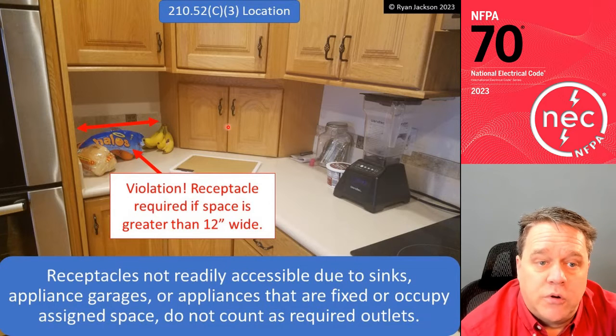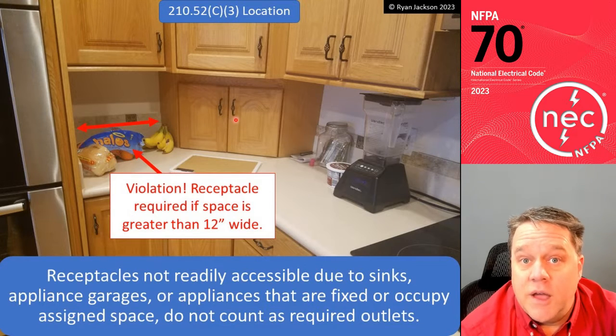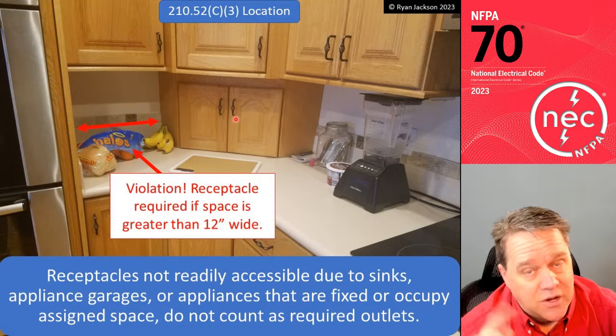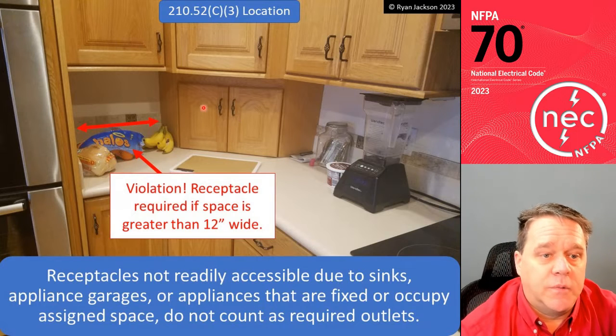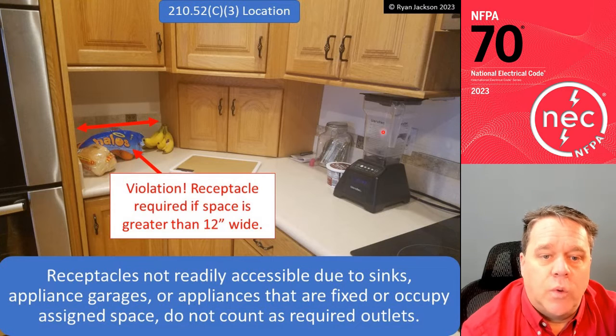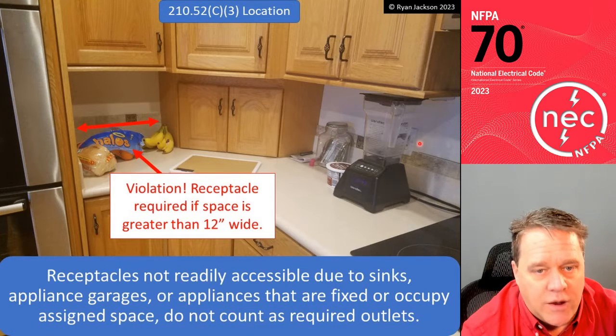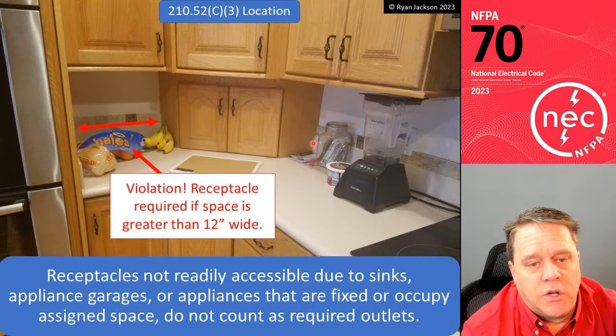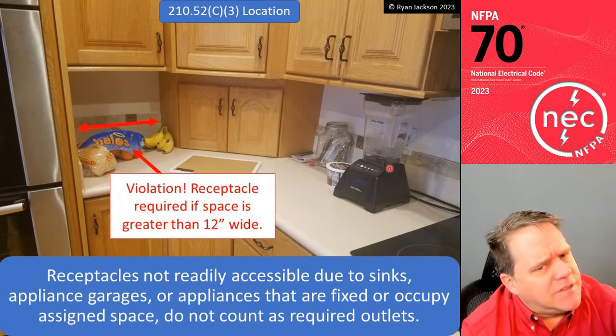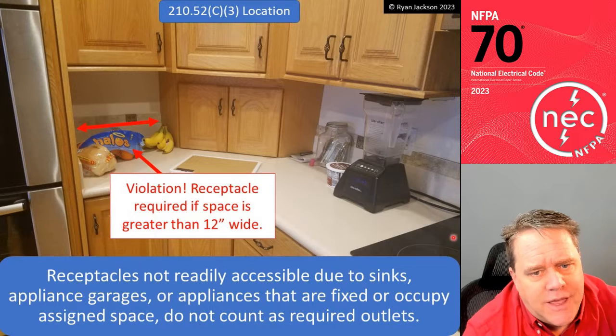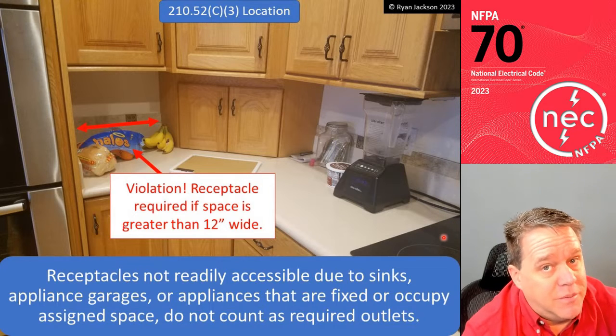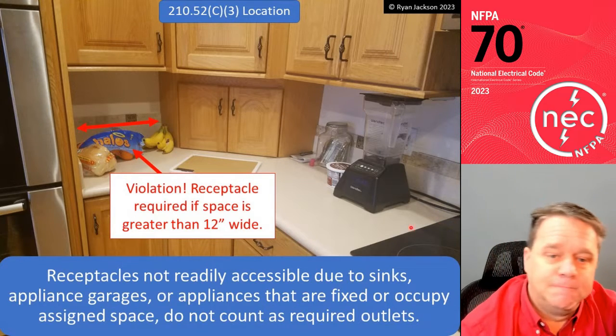So if you want to put a receptacle or two inside that appliance garage, be my guest. They don't count as required receptacles. You still need to have a receptacle here on the left and one near the blender over here on the right. And you can see that we do have a receptacle plugged in right there, so we're good to go. Not too keen on having the cord laying on top of the cooktop here. Probably not the best idea, but hey, it is what it is.